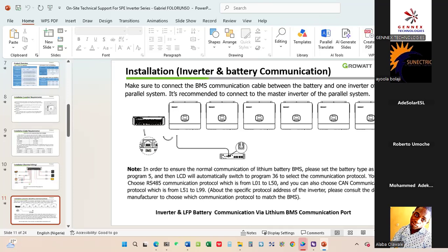Like my colleague mentioned, if you get to Protocol 36, there's a number ranging from L01 to L99. If you look at L01 to L50, it means you're working with RS485 ports, but when you work with 51 to 99, you're working with CAN, and you cannot mix it. More often, Growatt understands the language of CAN - Control Area Network. So you go to program 5, pick 36, then from there you take the protocol.